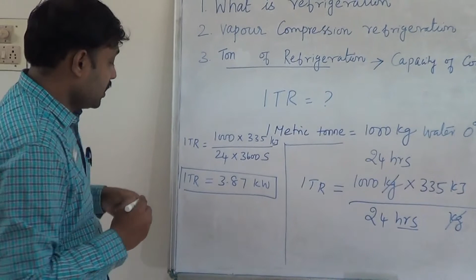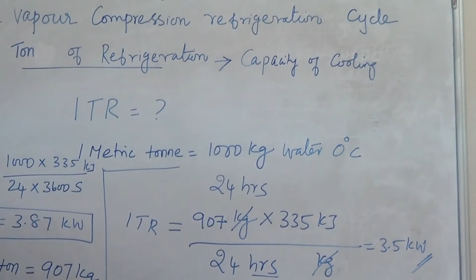This is 1 ton in the metric system, because 1 metric ton is 1000 kg. But since this is denoted by the design engineers in the US, 1 US ton is equated as 907 kg. So if I substitute the US ton instead of the metric ton, it will be 907 kg, and we will have the value as 3.5 kilowatt. So to use a generalized terminology for defining the cooling capacity of the refrigeration system, worldwide 1 ton of refrigeration is considered to be 3.5 kilowatt.